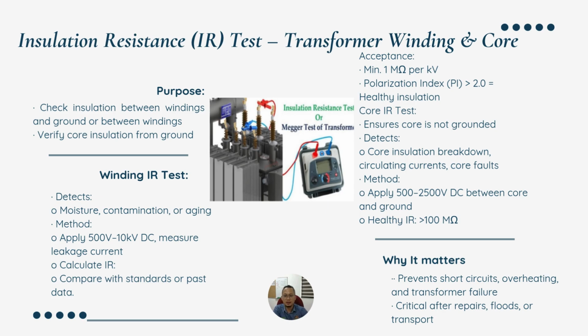Another important test is the insulation resistance test, which checks the insulation between winding and the ground, as well as between different windings. We apply a DC voltage to measure the insulation resistance. Healthy insulation shows high resistance, usually measured in megaohms. This test is vital for preventing short circuits, overheating, and transformer failure, especially after repairs, flood, or transport.